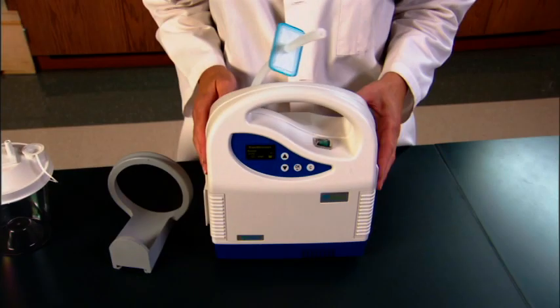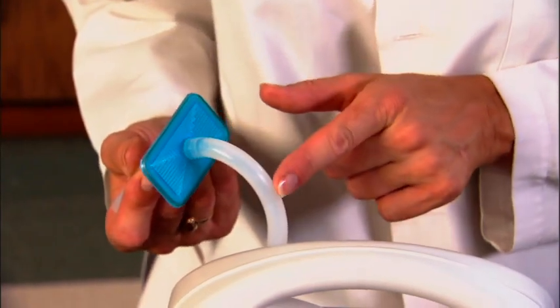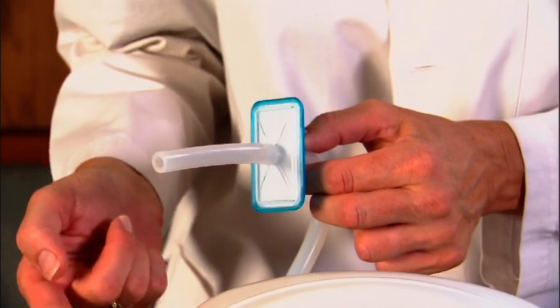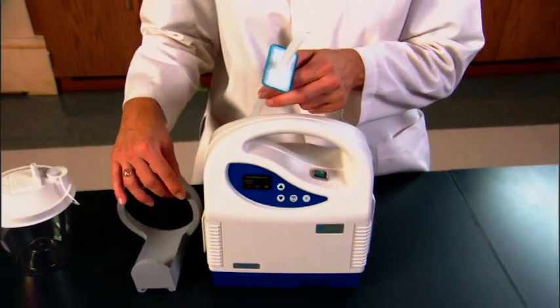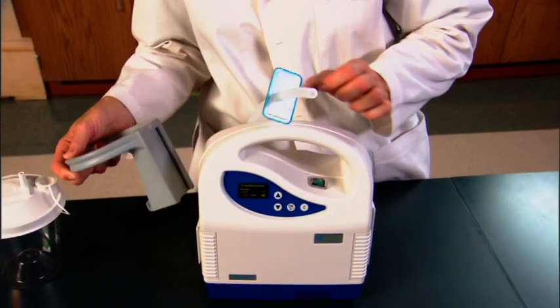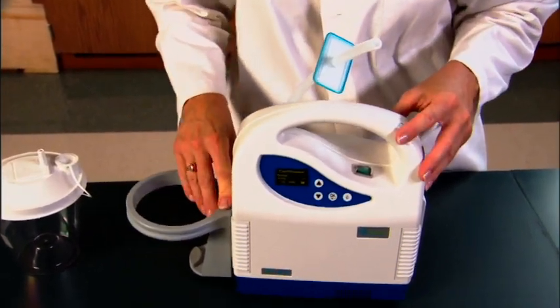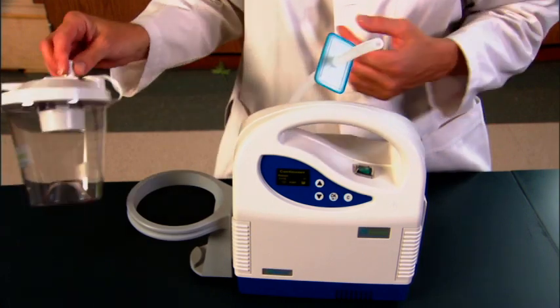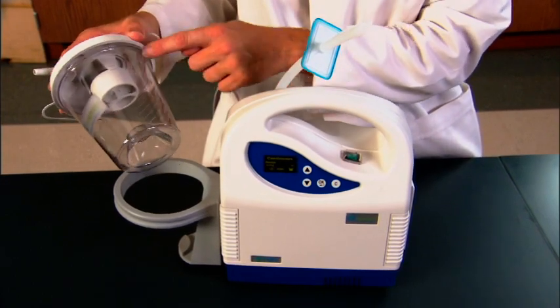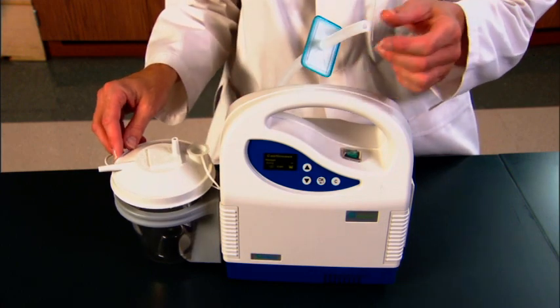Assembling the Prospera pump is quite simple. You have the filter tubing — make sure that the blue side goes to the pump and the white side goes to the canister; it won't work the other way around. Place the gray canister ring on the side of the pump, and then place the canister inside the gray ring. Make sure that the seal is tight at the top, because if you're going to have an open system alarm, this most frequently will be where it comes from — from a poor seal.